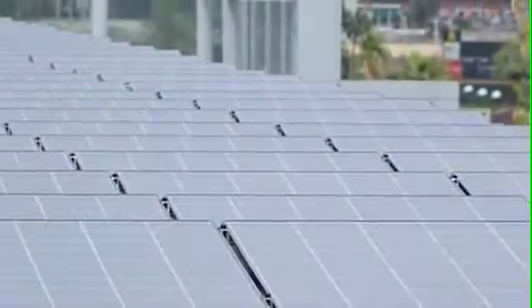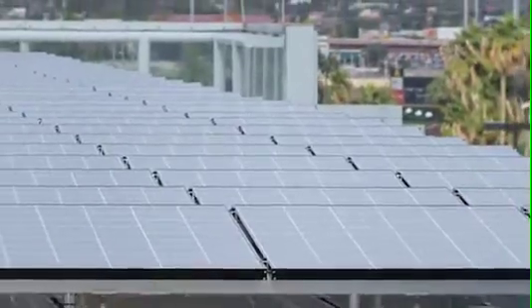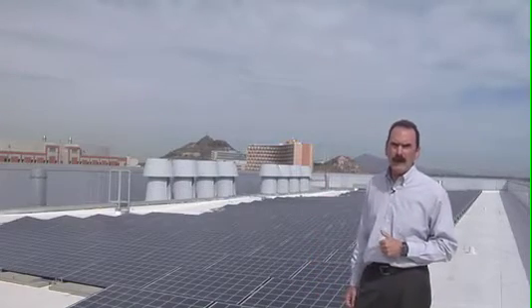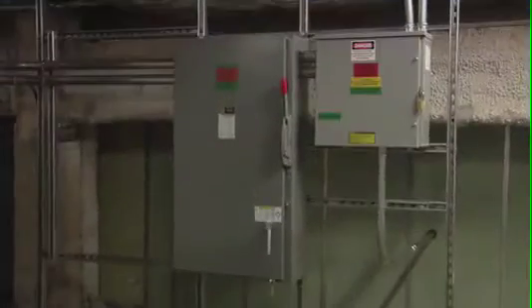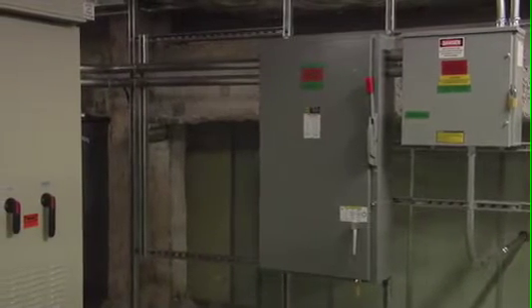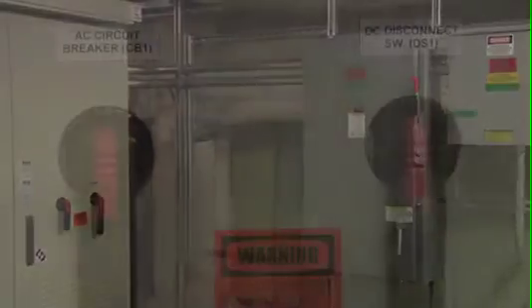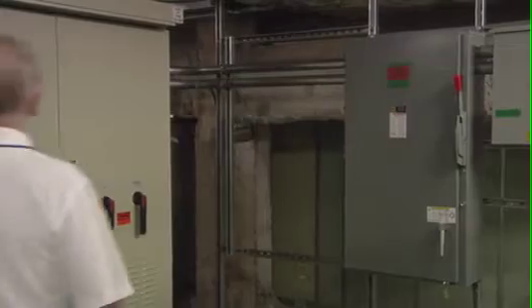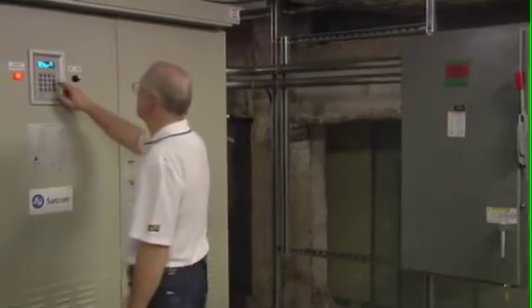The 20 panels it takes to reach 400 volts is called an array. Each of the arrays are hooked together in parallel and run downstairs to a voltage regulator, so we maintain that 400 volts throughout the day. Different parts of the day, more or less power will be generated. Right now, at midday, we're generating the peak we possibly can.